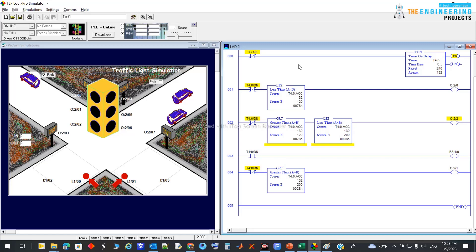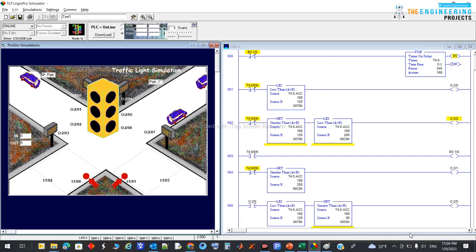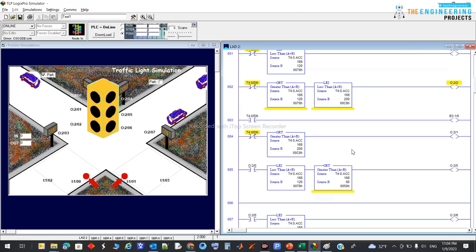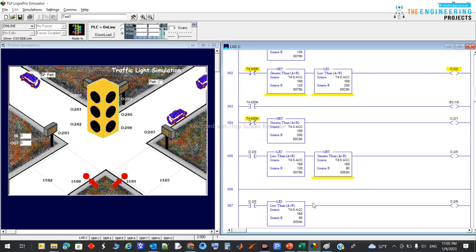This timer has two periods — one for each side. So I'm adding a new line here. As you can see, I've added this input: if the timer is not done, I will write the logic for the period in which this side is red. I've added the output for the other side — if it is between 8 and 12 seconds I'll add the amber, and if it is within the first 8 seconds I'll add the green.